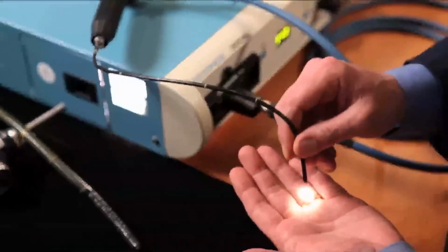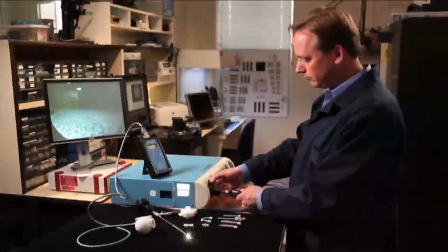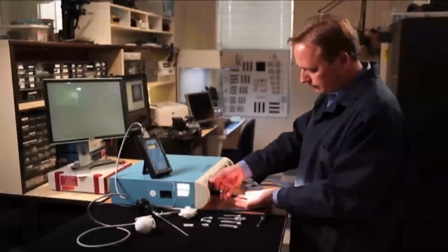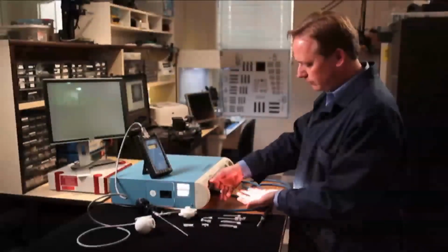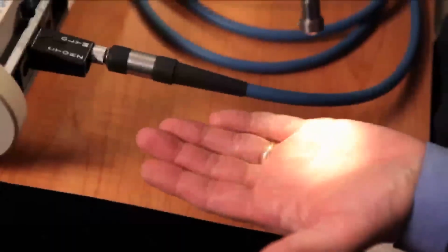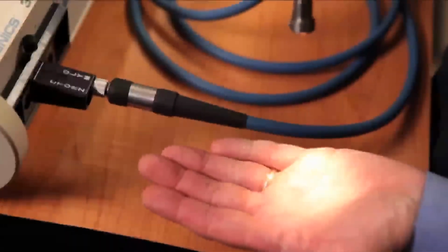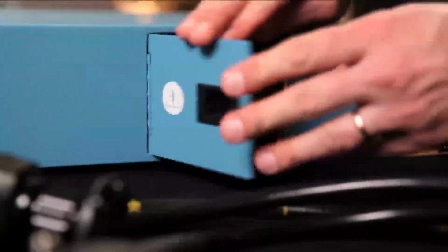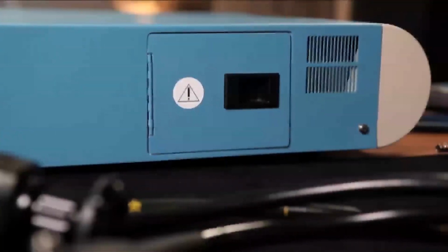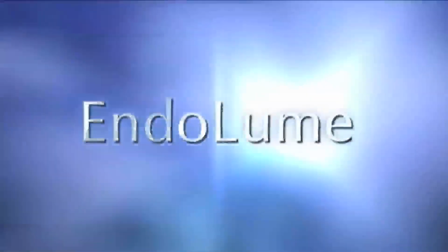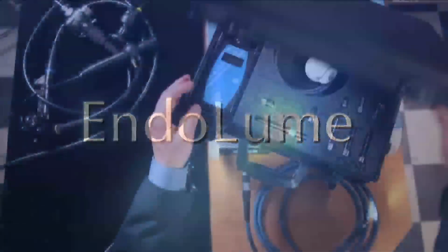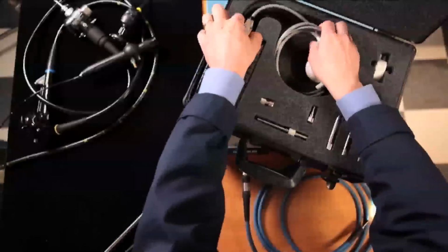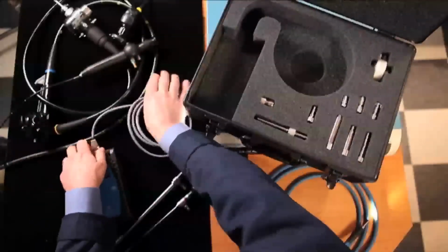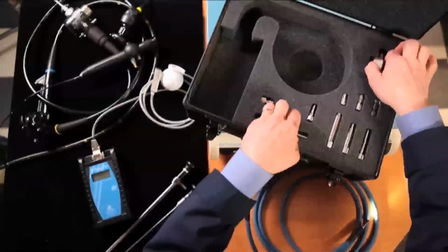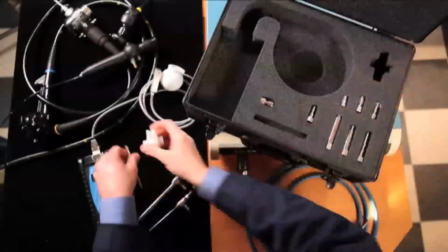It is often difficult to determine whether an insufficient light problem is due to a defective bulb, a misaligned light source, or a defective or damaged light cable, or if the problem is in the endoscope itself. Testing each of the components independently allows the biomedical engineer to quickly locate the source of the problem and fix it. The EndoLume endoscope system photometer isolates endoscopic illumination failure points and quickly assists in a cost-effective approach to repair, all in a simple-to-operate portable kit.